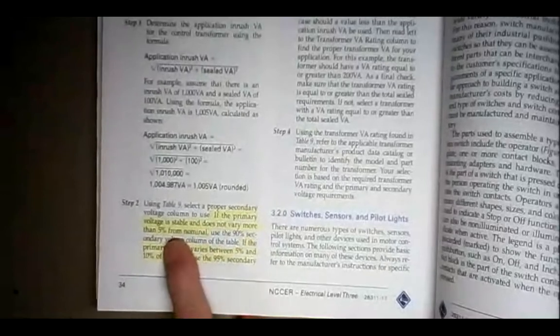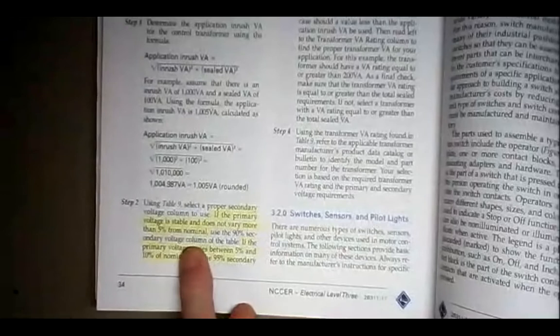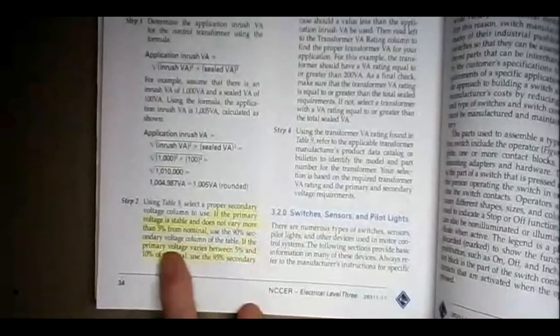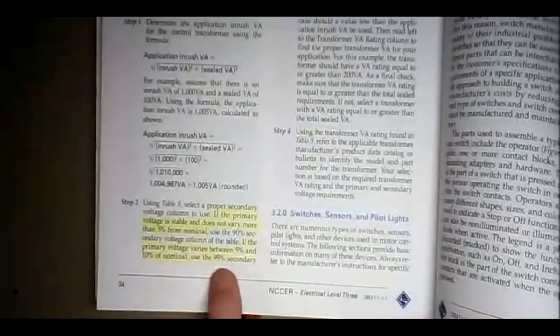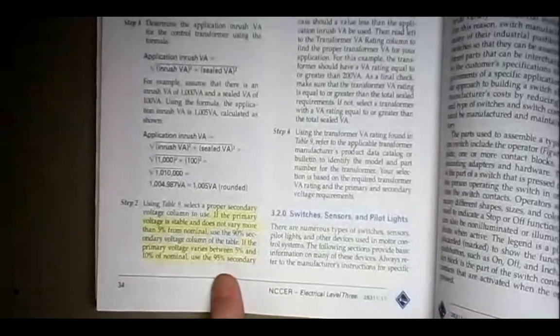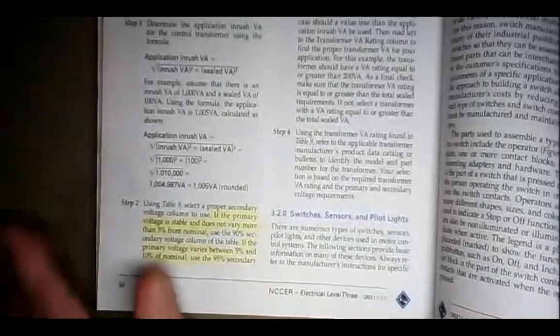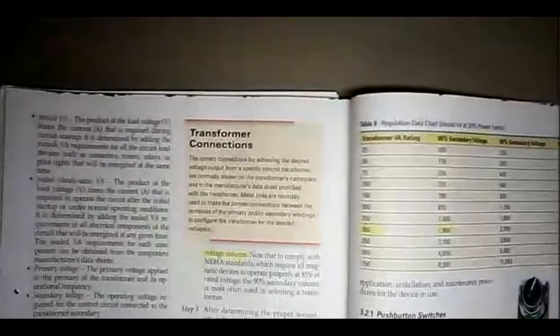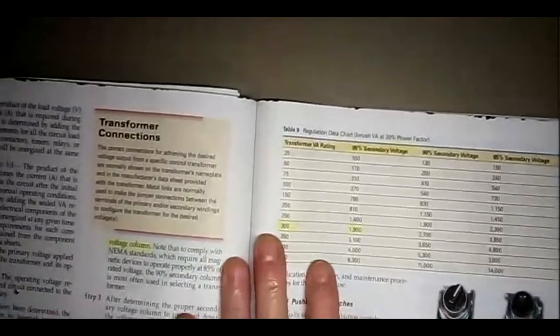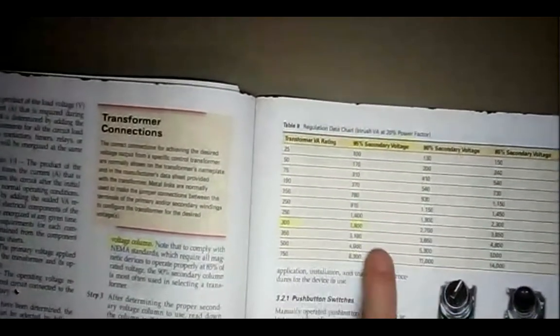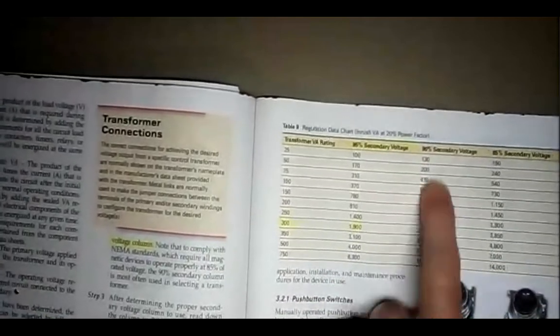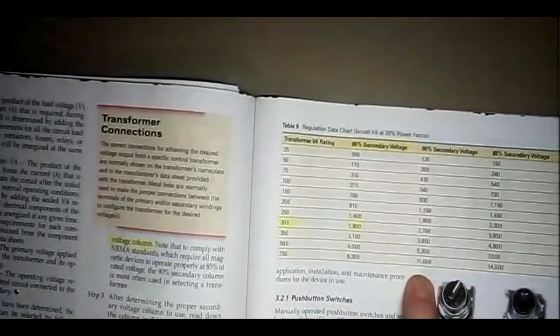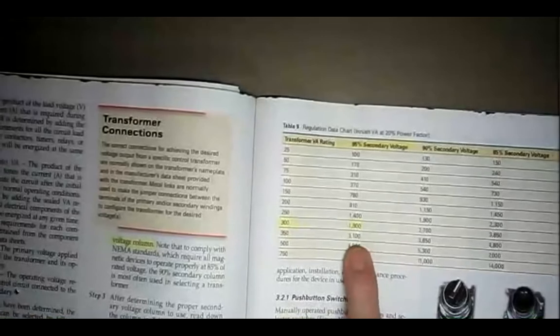If the primary voltage is stable and does not vary more than 5% from nominal, use the 90% secondary voltage column of the table. If the primary voltage varies between 5 and 10% of normal, use the 95% secondary voltage column. And it said voltage column up here on the right-hand side. So here's page 35. This is that table 9 that they were talking about. And they're saying that if it's stable, use the 90% secondary voltage. If it fluctuates between 5 and 10% of normal, then you're going to want to use this 95% secondary voltage.